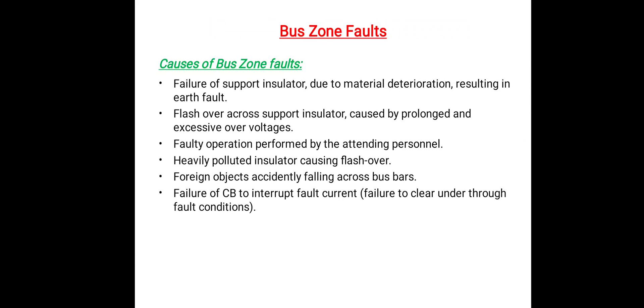The next topic is the basic causes for bus zone faults. According to statistical information, the majority of faults are basically single-phase in nature and temporary in character. The causes of this type of faults are: failure of support insulator, flashover across support insulator, faulty operations performed by attending personnel, foreign objects accidentally falling across the bus bars, and failure of circuit breakers to interrupt fault current or failure to clear under through-fault current. The clearing of a bus fault requires the opening of all circuits branching from the faulty bus or bus section.